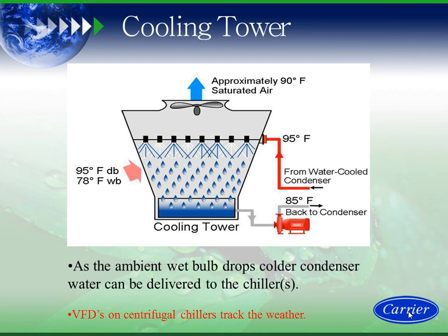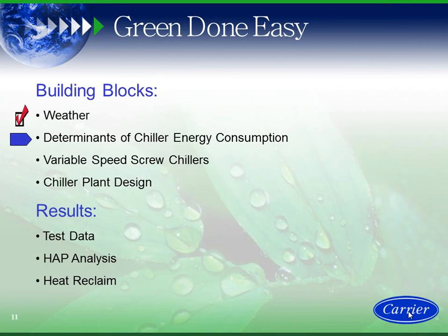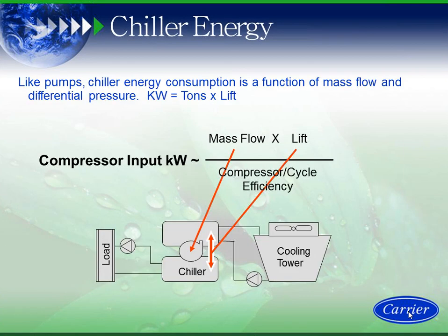A centrifugal with a VFD is a part lift device. It's not a part load device, it's a part lift device. So VFDs track the weather. That's one of the key pieces we want to know. When we start talking about chiller energy consumption itself, we have the mass flow, which is the refrigerant flow, times the lift. And the lift is very important when we're determining chiller efficiency in a standard chiller plant.